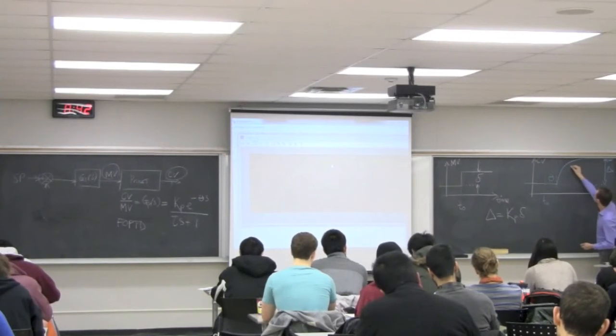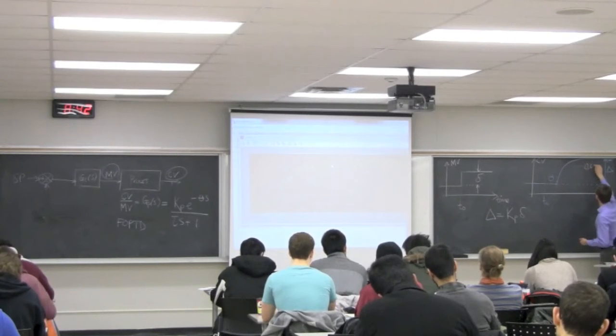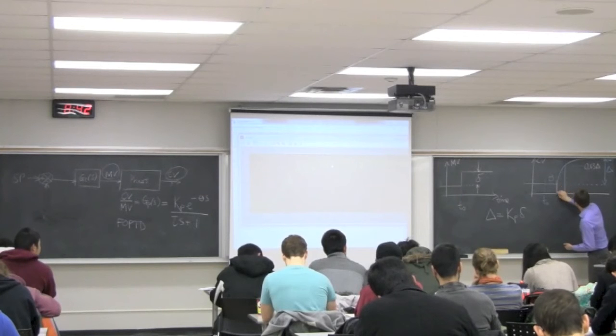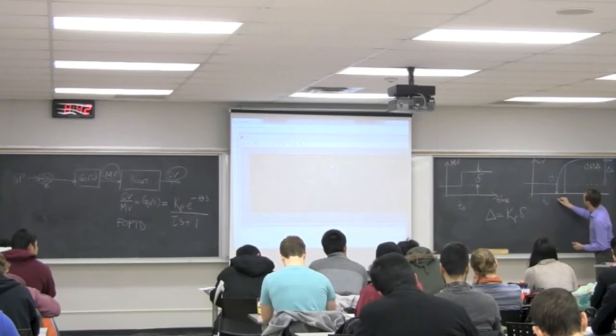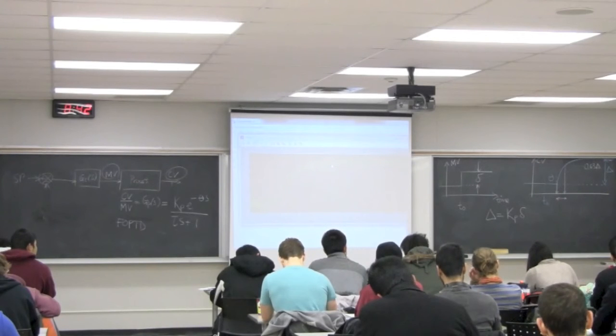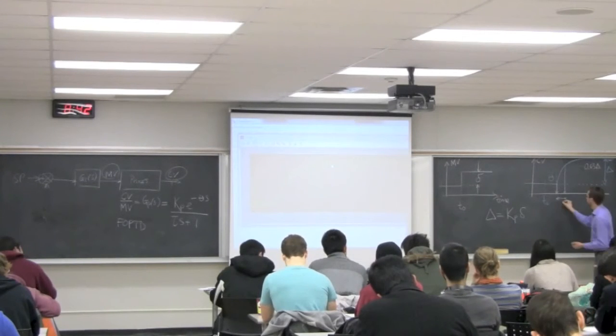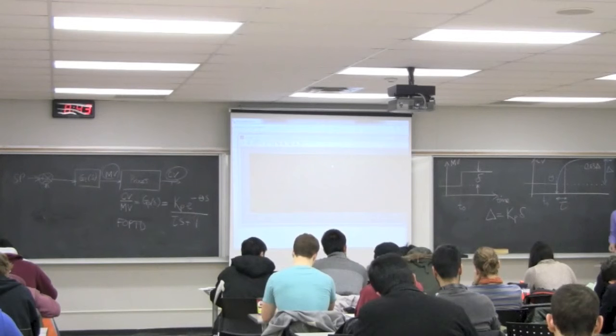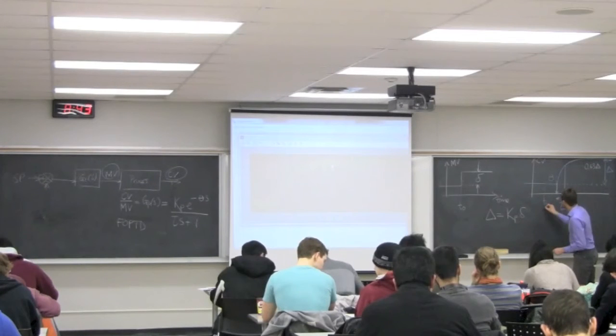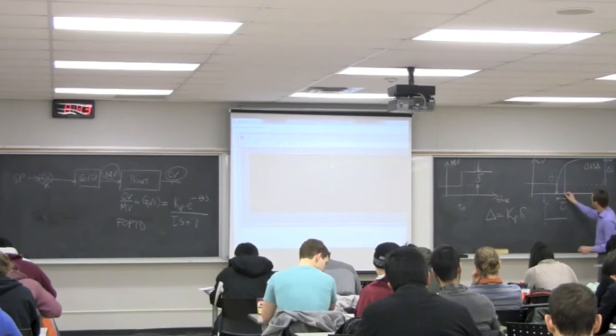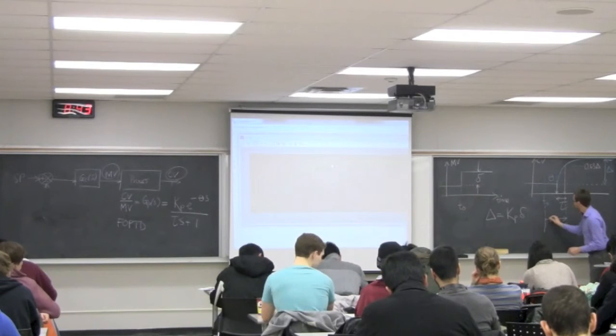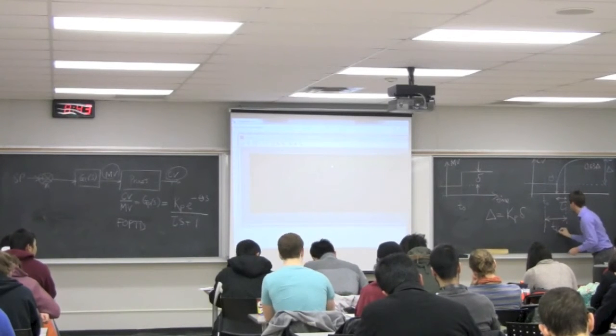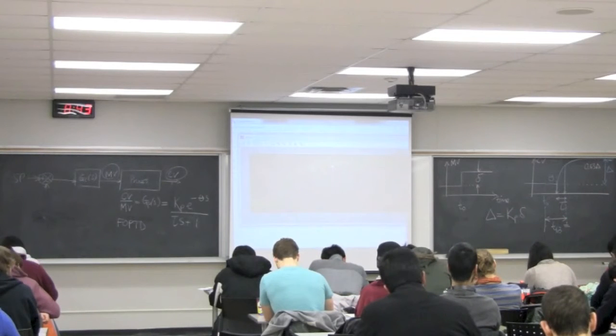For that duration of time theta, I will see actually no change in CV. There's a pure dead time in my system, and then this rises in the first-order manner. That total rise, this distance here, we call delta. Capital delta is the total rise time. We said last time that delta, capital delta, is equal to Kp times lowercase delta. Lowercase delta, you recall, was the amount by which we increased the manipulated variable. The theta then is that pure time delay. If we wait 63% of delta, so 63% of delta would be somewhere around here. We drop this down, this distance over here from when it starts to rise, so when it reaches 63% of the rise time, that's my time constant tau.